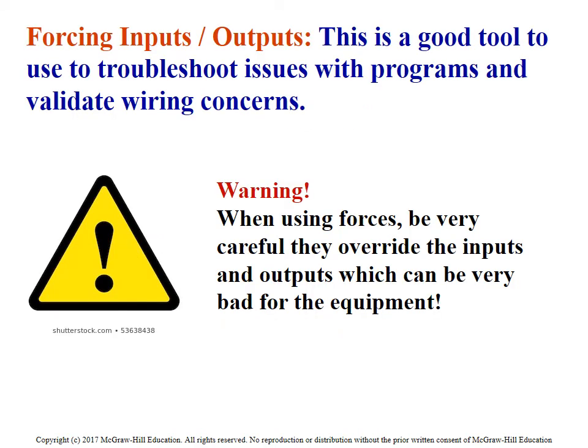So when we're talking about forcing inputs and outputs, this is a good tool to use for troubleshooting issues with programs and validating wiring concerns. But I have to throw a huge warning out there to you guys. This is an area that a lot of people struggle with. It's pretty easy to set up a force into a program. It's even easier to forget about it. So you come into a program, you set up a force, you force an input or an output on, and at that very moment that force is enabled, and you forget about it.